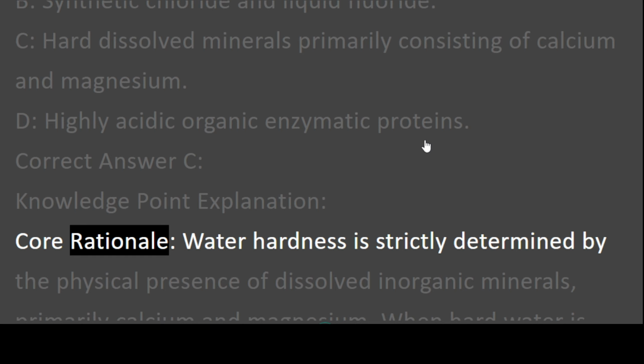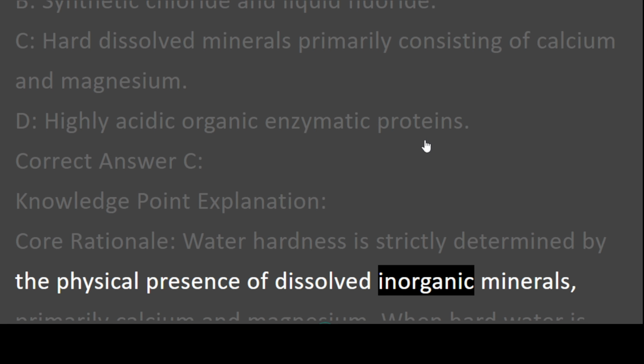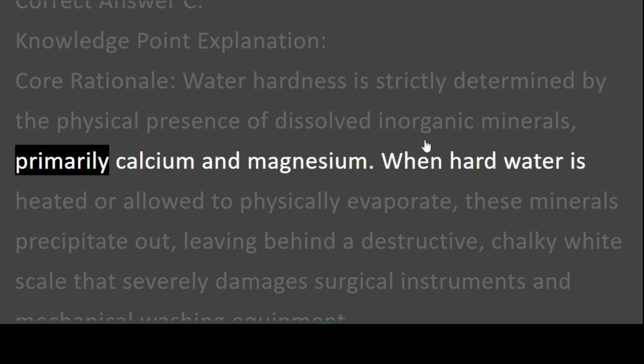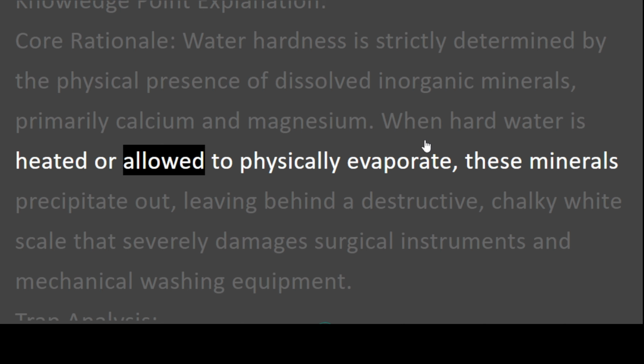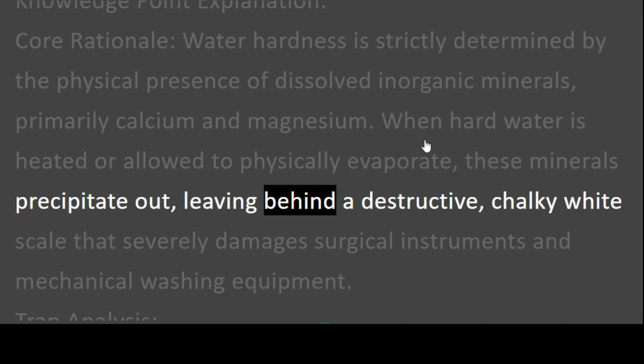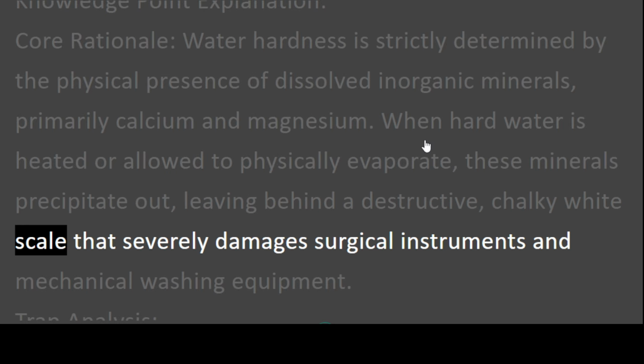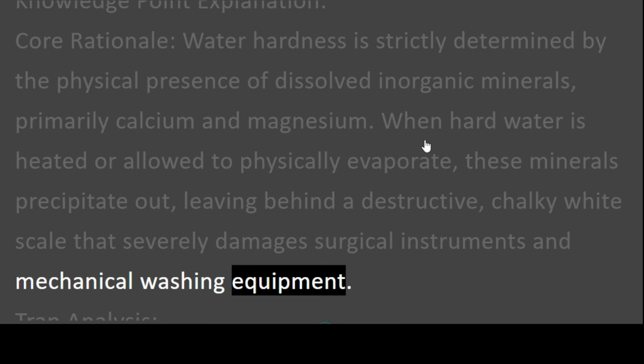Core rationale. Water hardness is strictly determined by the physical presence of dissolved inorganic minerals, primarily calcium and magnesium. When hard water is heated or allowed to physically evaporate, these minerals precipitate out, leaving behind a destructive, chalky white scale that severely damages surgical instruments and mechanical washing equipment.